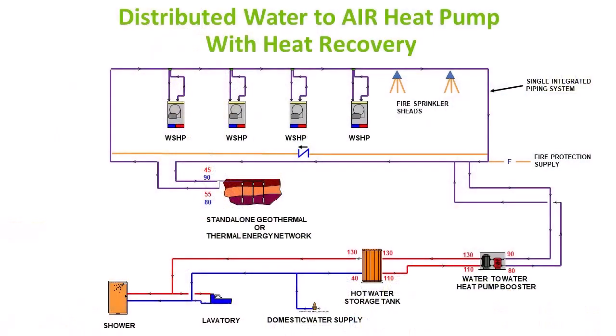And here's what we would do if we did it with geothermal. We're going to replace these guys here, the cooling tower, the boiler, and that air source heat pump with a single geothermal system, and we're going to do heat recovery. Pretty cool, huh?